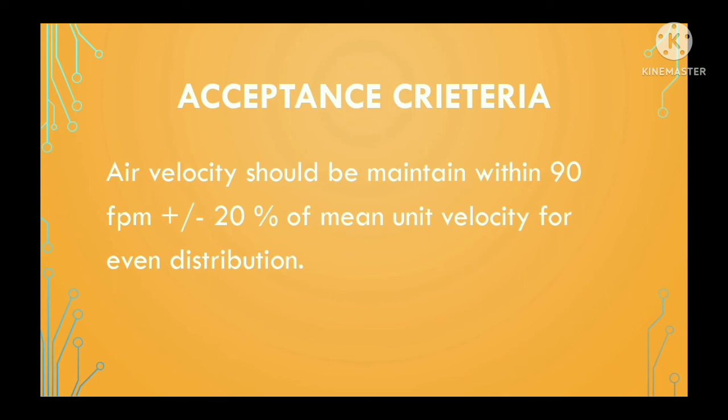Next, we will see the acceptance criteria for air velocity check. Air velocity should be maintained within 90 feet per minute, plus or minus 20 percent of mean unit velocity, for even distribution of temperature.